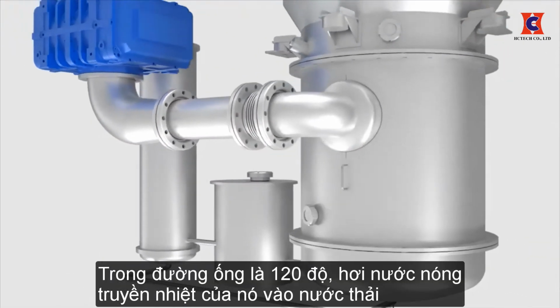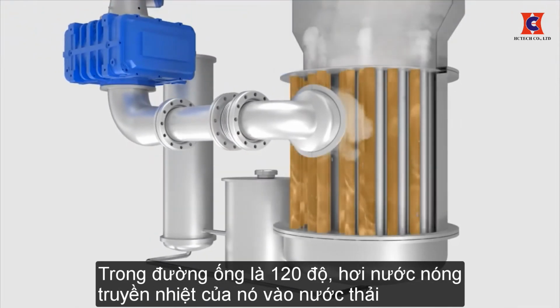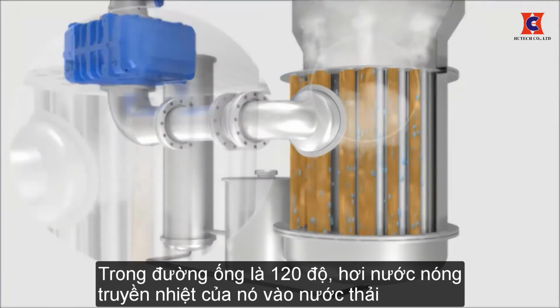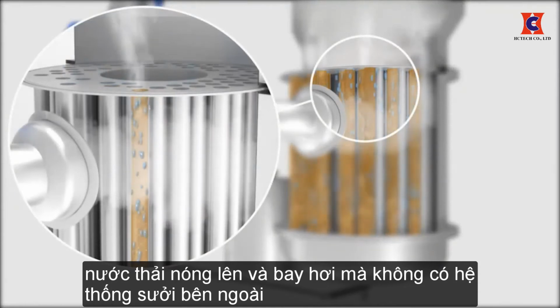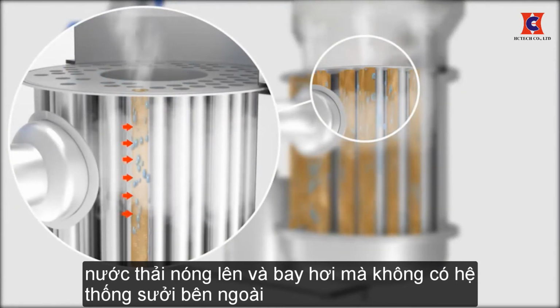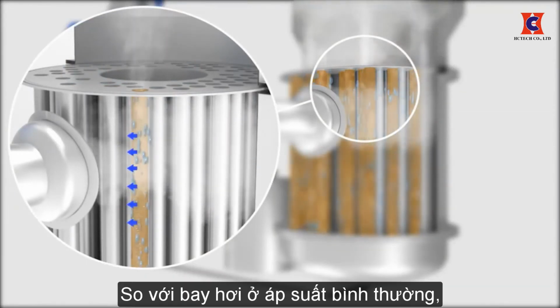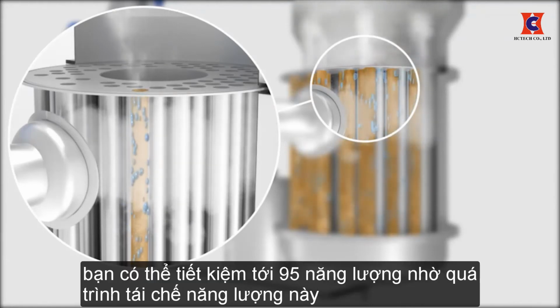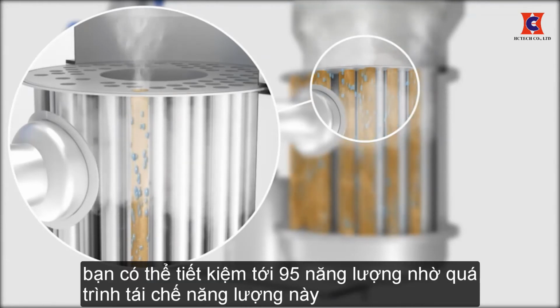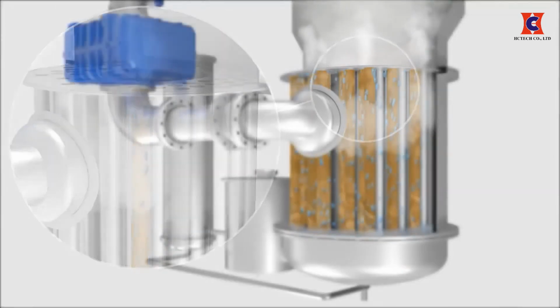In the bundle of pipes, the 120 degrees hot steam transfers its heat to the wastewater. The wastewater heats up and evaporates without external heating. Compared with evaporation at normal pressure, you can make up to 95% energy savings thanks to this process of recycling energy.